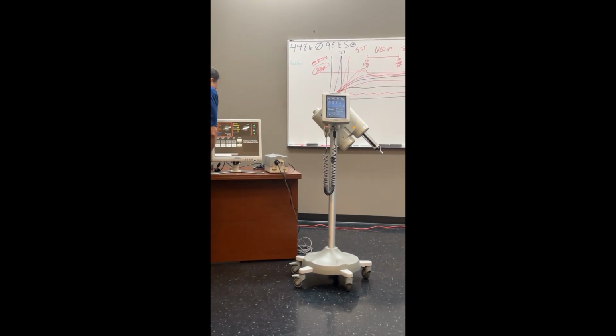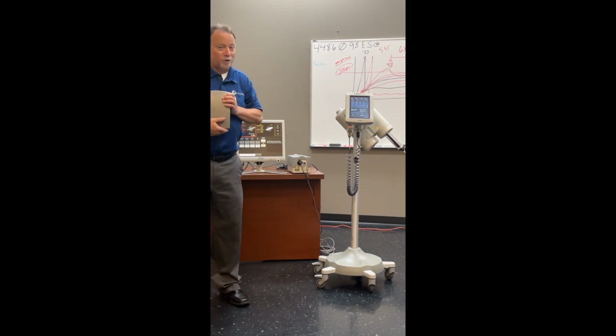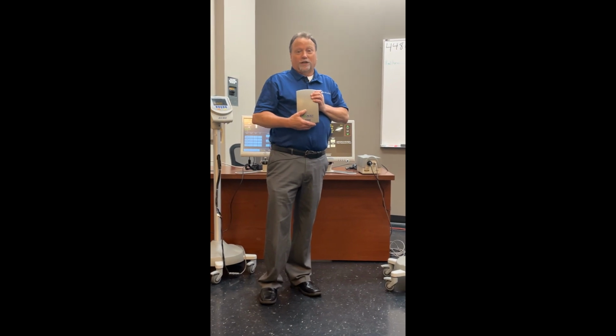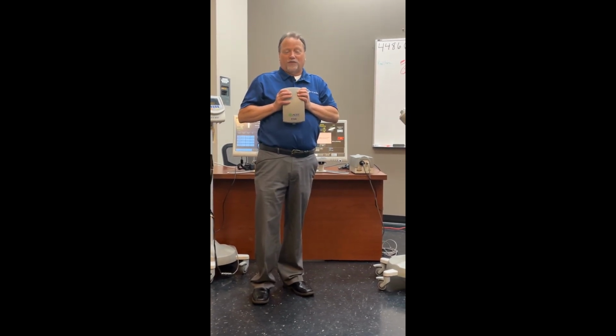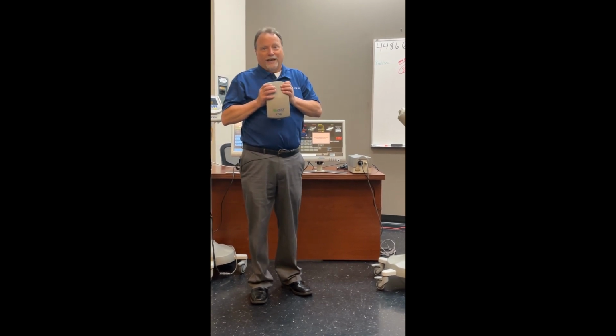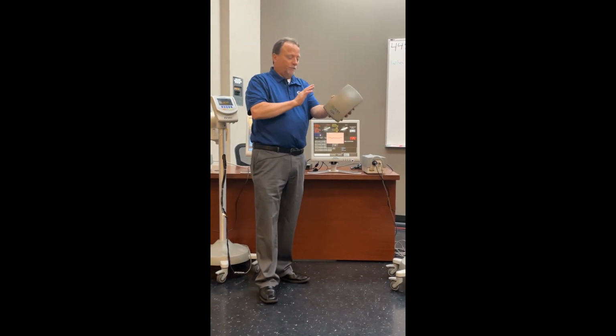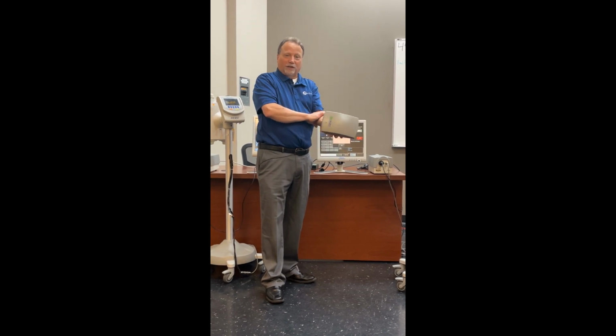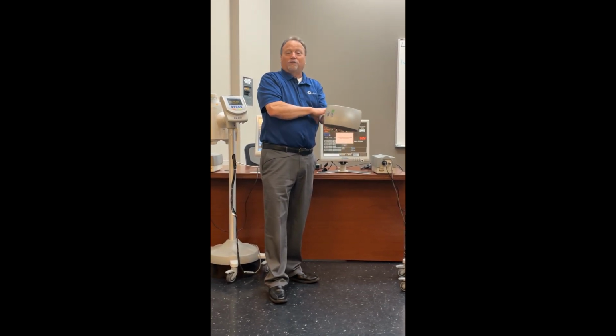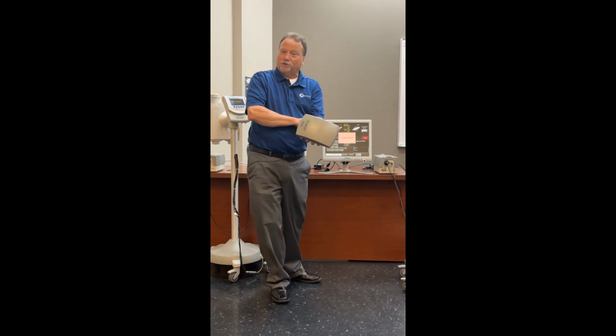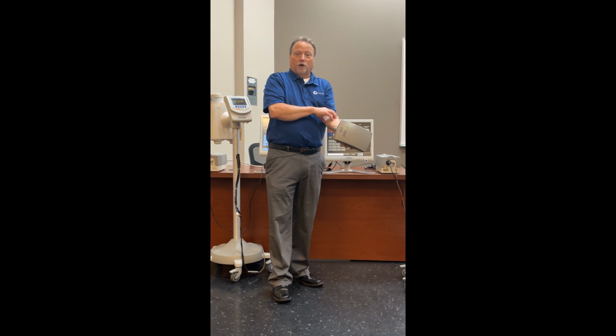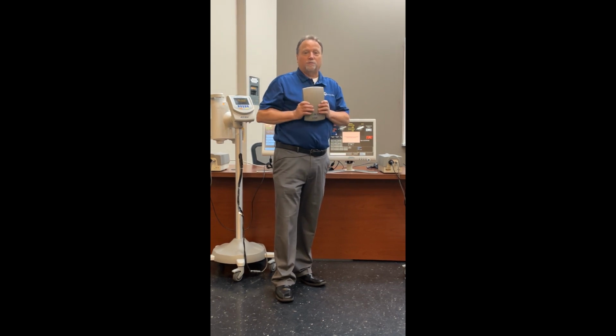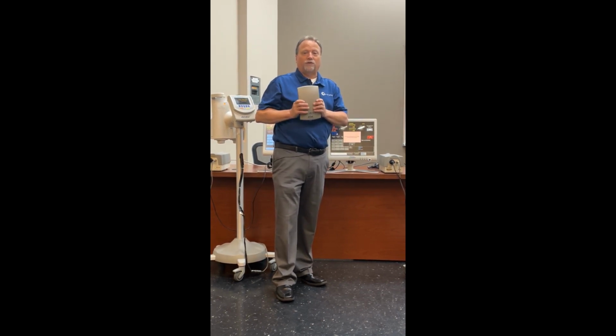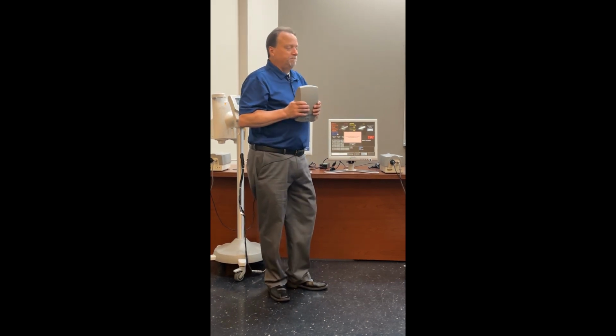Another feature these have is the, if I pronounce it correctly, extravasation detector. It's called EDA, extravasation detection analyzer. The way this works is a patch that goes onto the patient's arm, and it detects the resistance in the patient's arm. If you have a blown vein or the contrast saline is not going where it's supposed to go, then it's going to form a bubble on the arm, increasing or decreasing the resistance, and it'll give you an error. There is a test module for this that Acist does sell, but you have to go to their training to get it, and then purchase it.